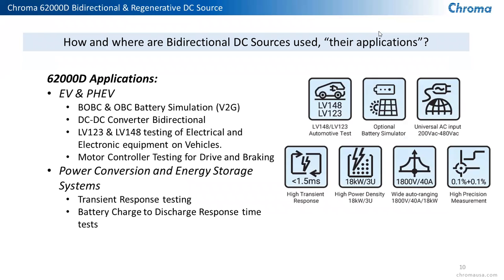We've also included in our software package the ability to do testing for LV123 and LV148 for the various electrical and electronic component testing for safety, as well as for functional testing of those devices. We've also incorporated motor control testing, where you can simulate the battery, using it as a source for the DC input to your motor controller that's driving your electric motor, and also in the reverse, when you're braking and you're putting power back into the battery, we can also absorb that power coming back as if it's a charging battery.